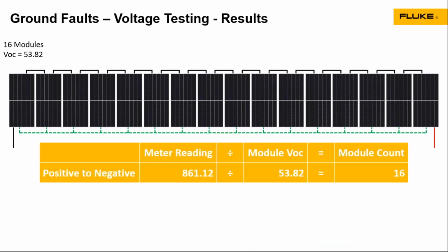When I go to look at my results, the positive to the negative, I get 861 volts. Divide that by 53, and I get 16 modules. That's the quantity of modules in the string. That's my expected open circuit voltage of the string. Now, keep in mind that I'm not going to get exact readings. It's going to be something plus or minus a little bit. We're not taking into account things like temperature or soiling on the array, or voltage drop on the wire. So it's not going to be perfect, but it's going to get us pretty close.